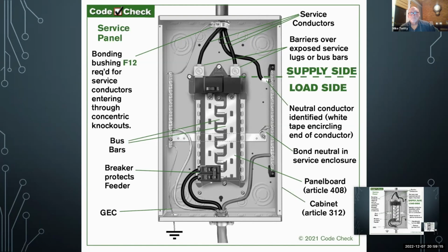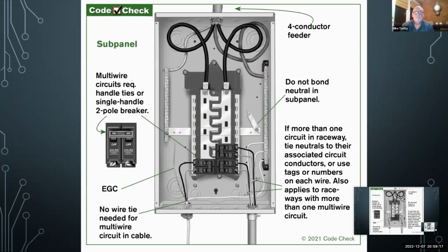Okay, we're going to look at a sub panel now. This is basically the same panel without a main breaker. This is a main lug panel now. Now you see the main bonding jumper has been removed from this terminal here. This one is a gray wire, it doesn't have the white tape on it, but this is your service neutral. These are your branch circuit neutrals, and they're all over here. Your equipment grounds go on this side. Now they have to be separated.